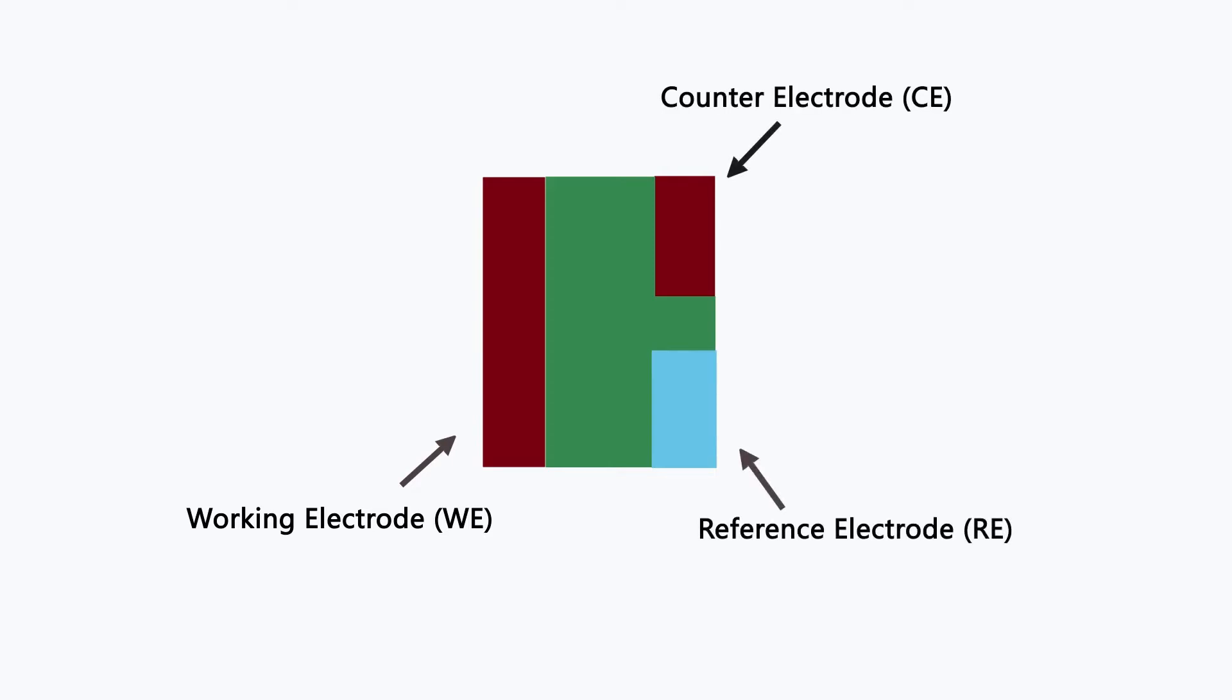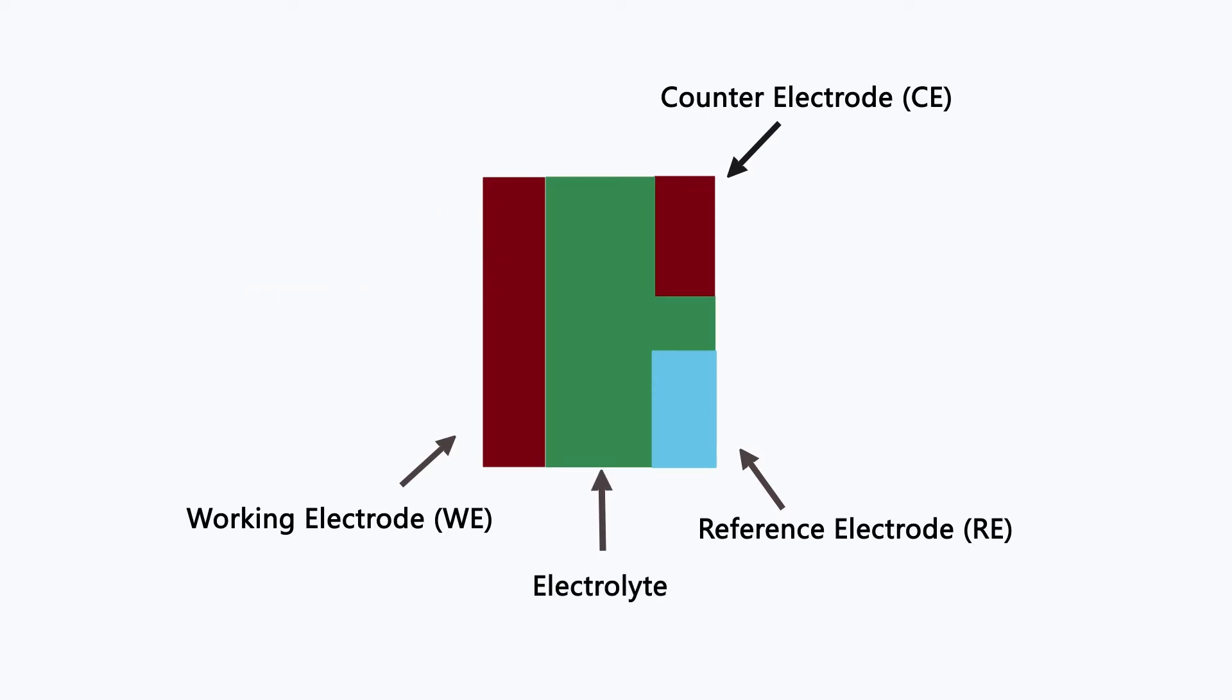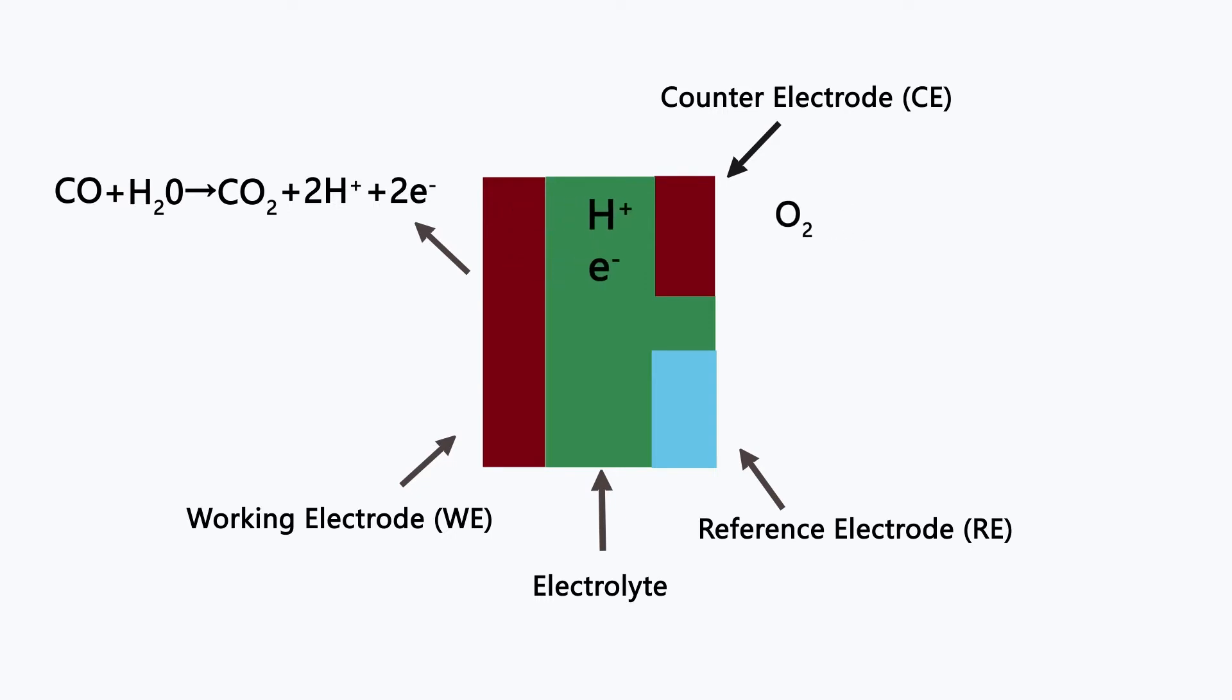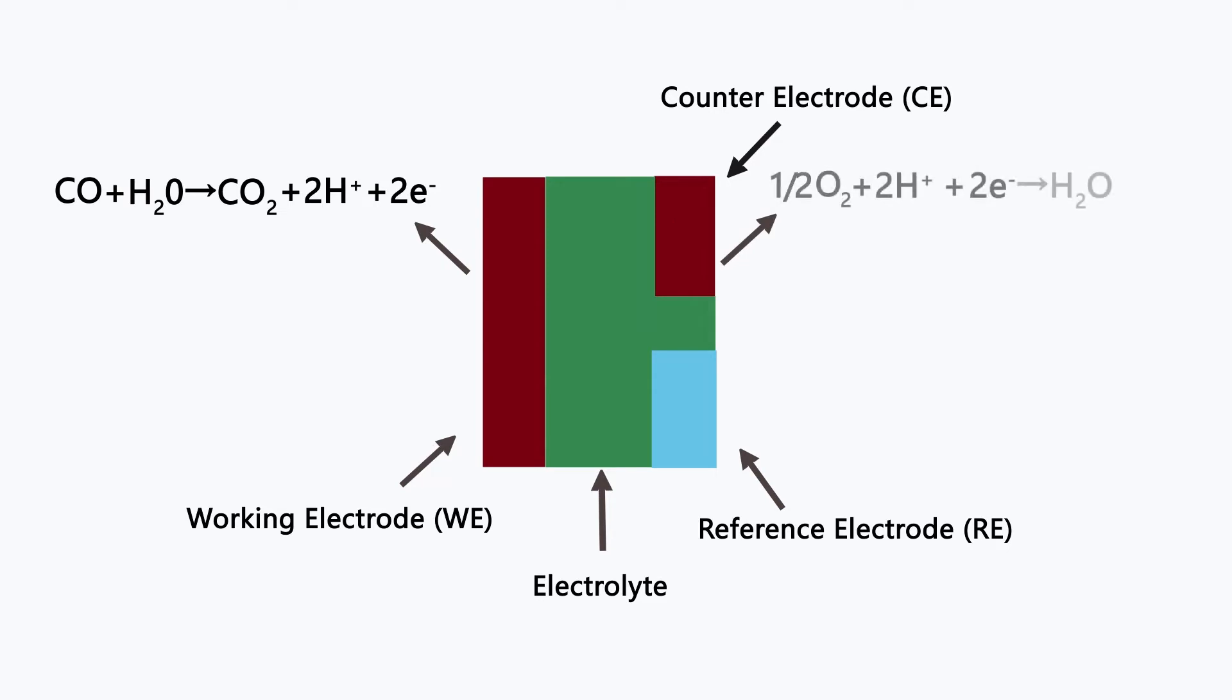When carbon monoxide comes into contact with the working electrode, an oxidation reaction occurs, producing carbon dioxide and hydrogen ions, and generating electrons. The generated hydrogen ions and electrons then move to the counter electrode and react with oxygen to produce water.